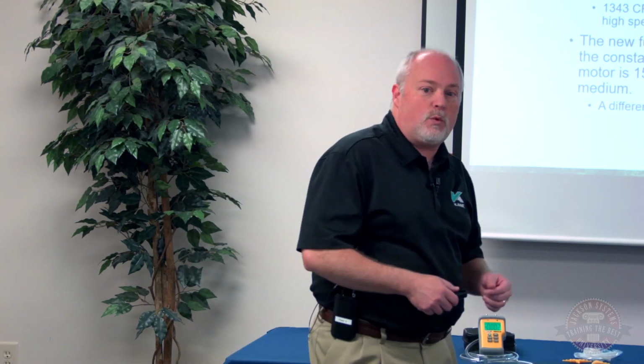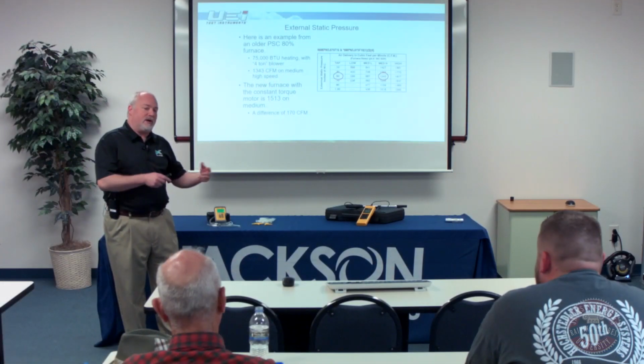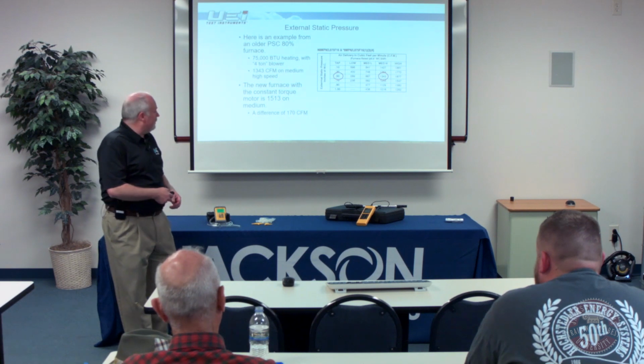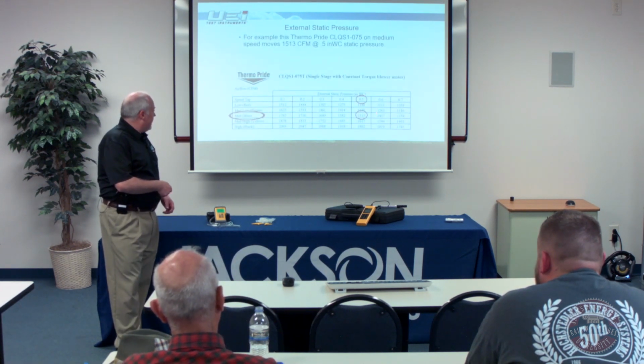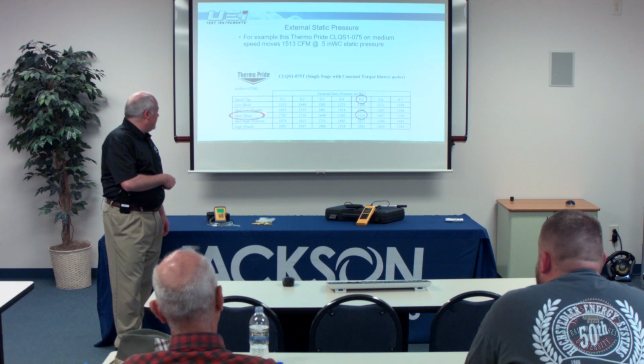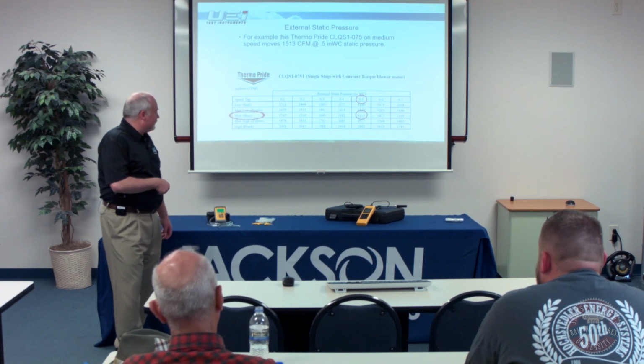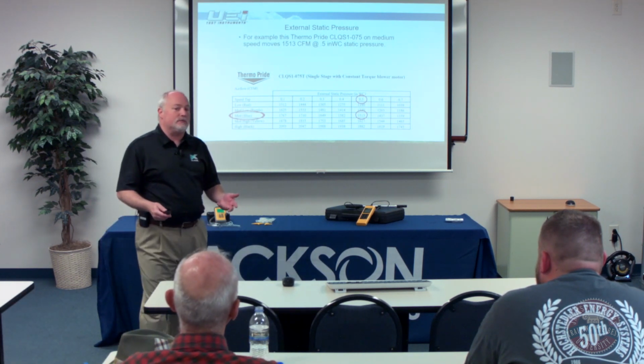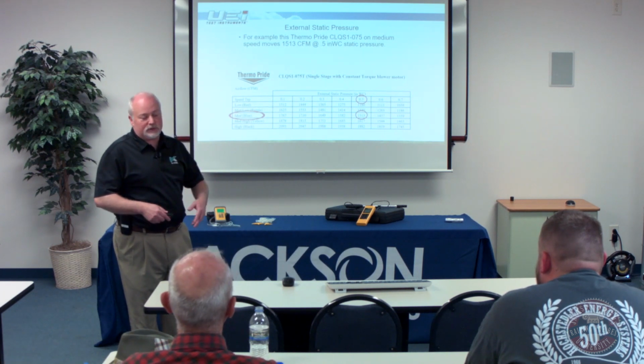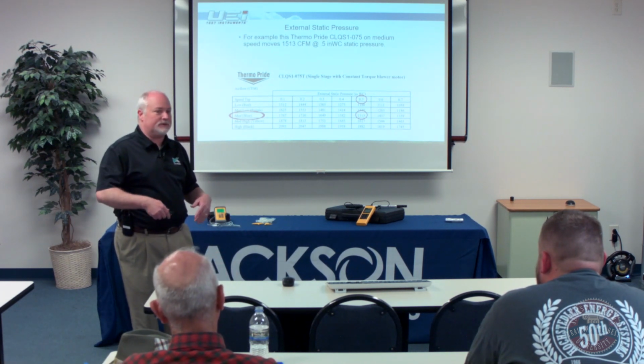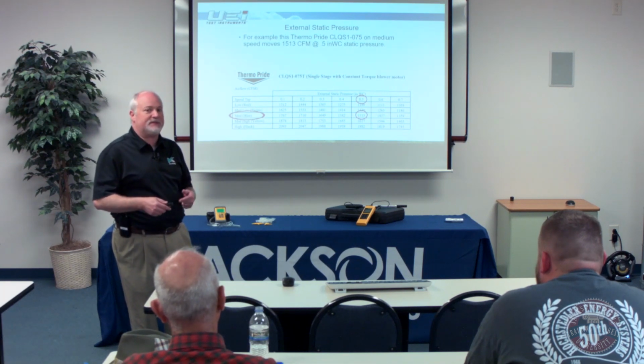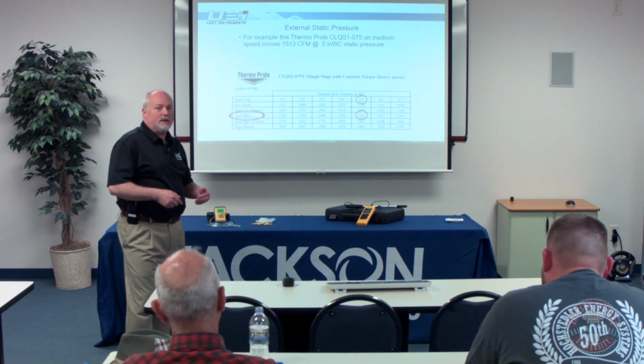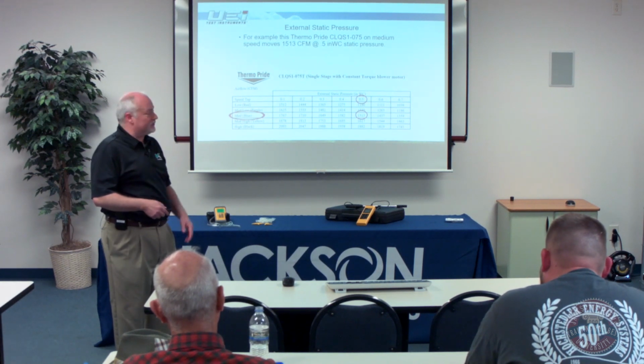We can look at the old piece of equipment, do an external static pressure test on it, find out what CFM it's moving, find out what the new one's going to move, and maybe we look at our chart and we say, hey, I need to select a different speed tap. If I go to medium low, now I'm at 1,300 CFM versus 1,500. So that may solve an issue. So anytime you're troubleshooting, trying to figure out an airflow issue, whether it be noise or balancing the system, know what your pressure is, because it's going to give you a direction to go to look for your solution.